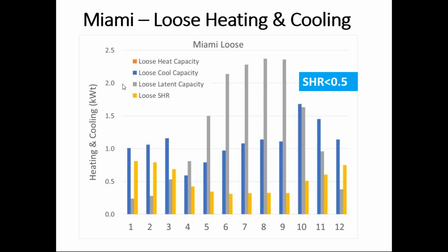We look at what this means as far as heating and cooling capacities. And this is thermal kilowatts, not electric. So it's not the plug end of the air conditioner. And the cooling capacity is the sensible cooling, the cooling needed for changing temperature. Miami needs no heating. So as you look at the report and see Urbana, you'll see quite a bit different. But what you see for contractor loose is that the sensible heat ratio is very, very low, well below 0.5. You've got to dehumidify in this house.